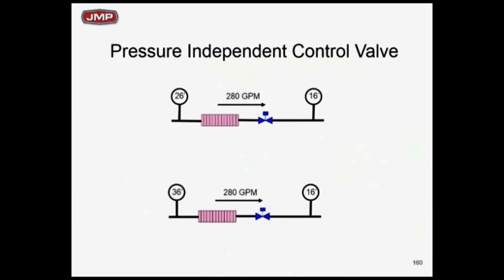One of my pet peeves is that I have people believing you can put a two-way valve in series with a flow limiter and do the same thing. By the way, before I leave this slide, you would, in theory, no longer need a balancing valve, because now you can look at the position of the two-way valve. And the particular PIC valves we have show GPM on the dial. You can actually read the GPM on the dial of a Bell & Gossett PIC valve. Where we are right now, we no longer need a balancing valve.